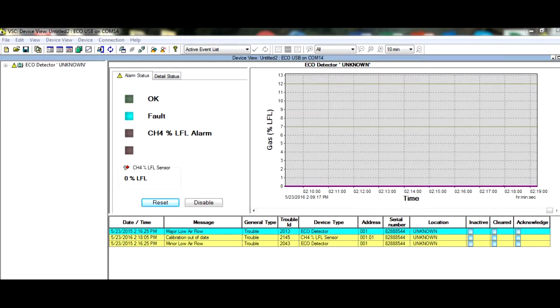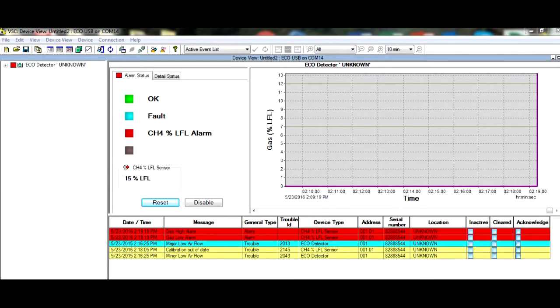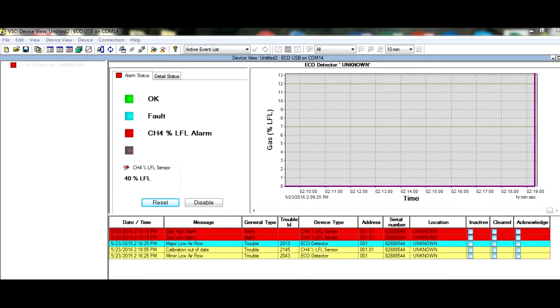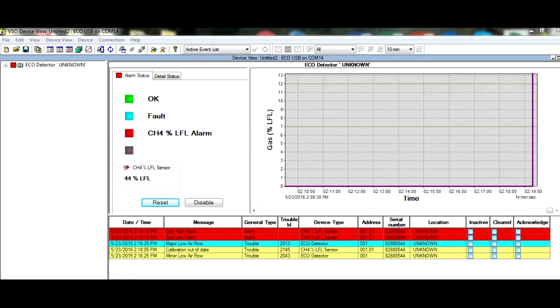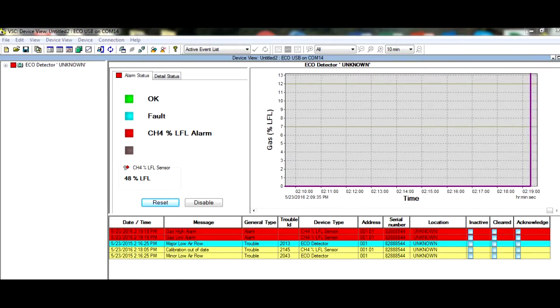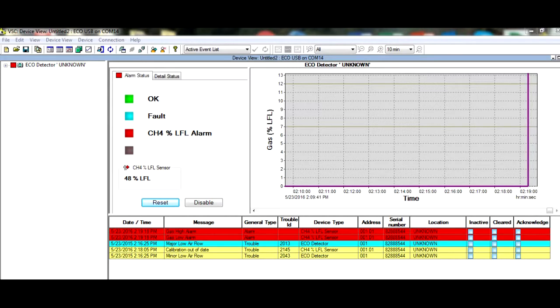As the gas is introduced, the detector goes into alarm. Confirm that alarm output circuits are functioning properly. Even though the detector is going into alarm, we still must span calibrate to clear the span calibration due fault.